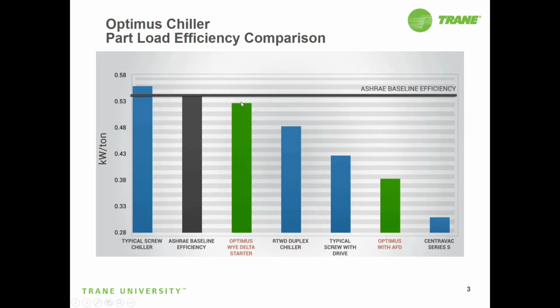Here's our Optimus with the Wye-Delta starter. So now we're running at part load, but remember that motor is still going to be turning at 3,450 RPM. The RTWD duplex at part load now is actually a little bit more efficient for the part loads, seeing how we only need to run one circuit possibly at a time on a dual circuit chiller. Here's your typical screw with a drive, which its efficiencies are in a really good range right here at part load as well. But the Optimus with the AFD really puts us kind of in a range of our own here. And part of that is because we have our conventional method of loading and unloading using a slide valve along with the frequency drive.